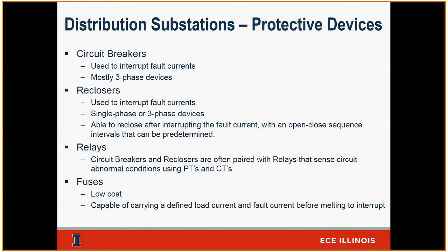Okay. So those were switches that you will find inside a substation. Other devices you will see in there are circuit breakers, reclosers, relays, and fuses. And let's talk about each one of those. So a circuit breaker, the difference between that and a switch, of course, are a few. One, it's capable of not only interrupting current, but also is capable of interrupting fault current, which is much, much larger in magnitude. So again, I'll give you an example.